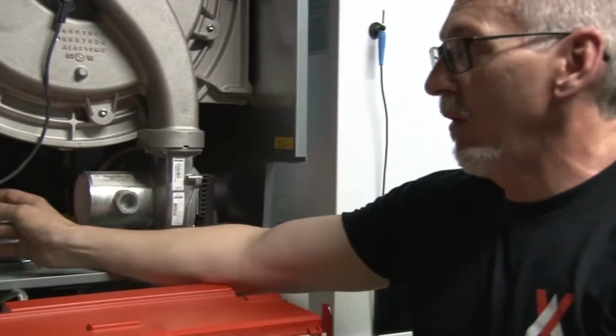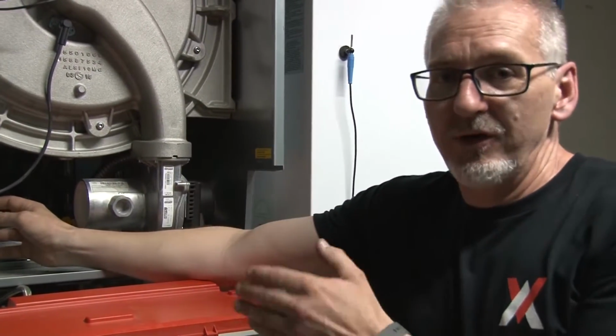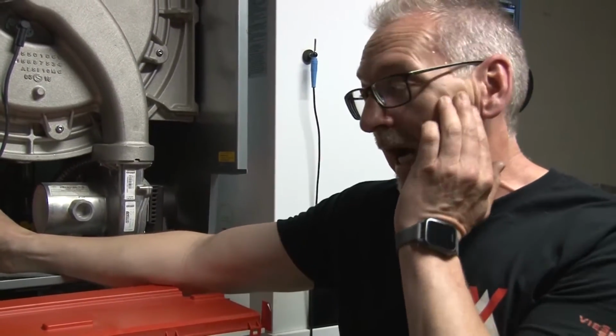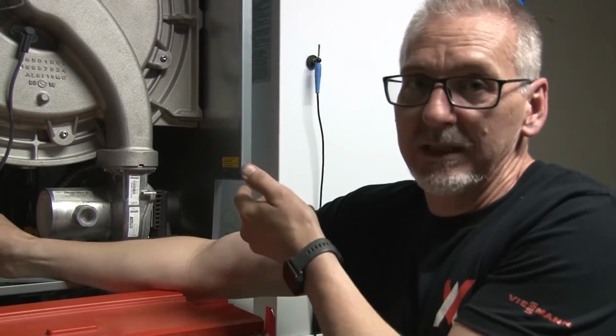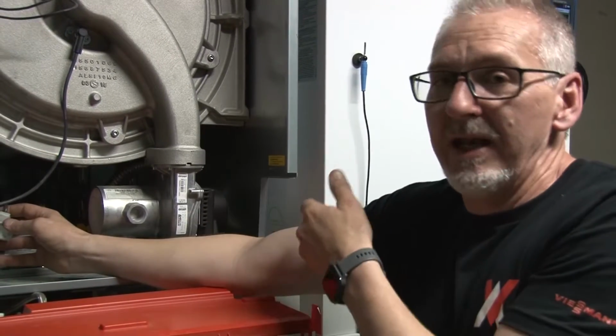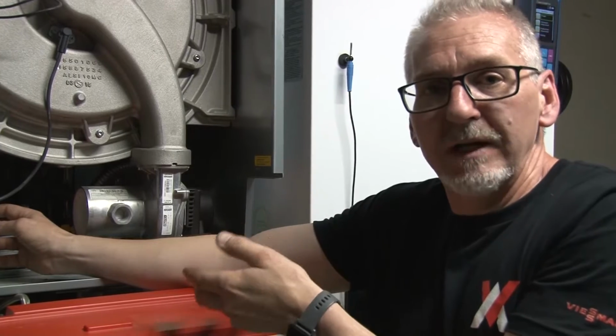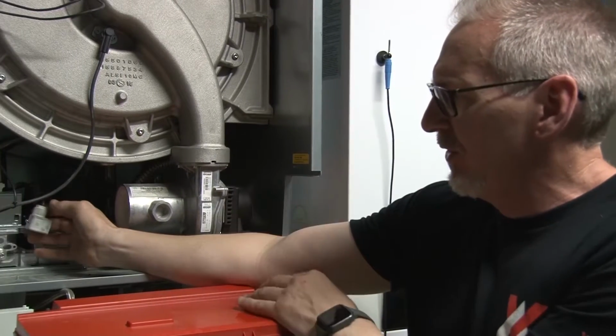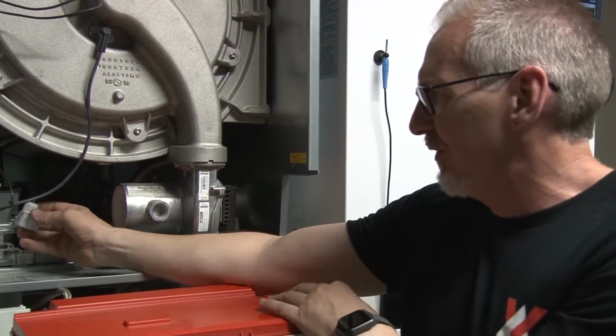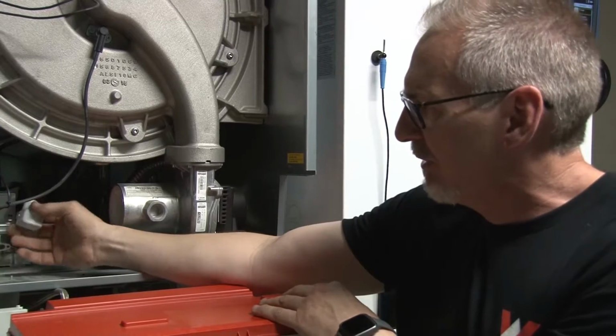So anything below 4 inches, the burner won't fire, but you're not going to get a fault on the boiler. It basically sits there to wait for that gas to come up above 4 inches, and then it allows the burner to operate if there's a call for heat. These are big boilers, so more important to make sure that gas pressure is accurate before the burner fires. So we have a low gas pressure switch there.